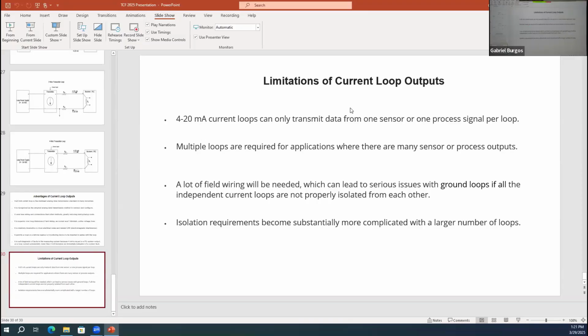Multiple loops are required for applications where there are many sensors. A lot of field wiring is needed. This is the key problem with multiple loops. You can get ground loops and other kinds of deleterious things. And as a result, isolation becomes more complicated. Now, one simple way, by the way, to get isolation, and I haven't put it on here, or maybe I should have, is to use a separate power supply for each loop, independent power. Lo and behold, as long as you don't have ground loops, you're in business. So it's something worth thinking about. And with that, I think I'm done. And I hope that you found something useful in all of my blabbering.